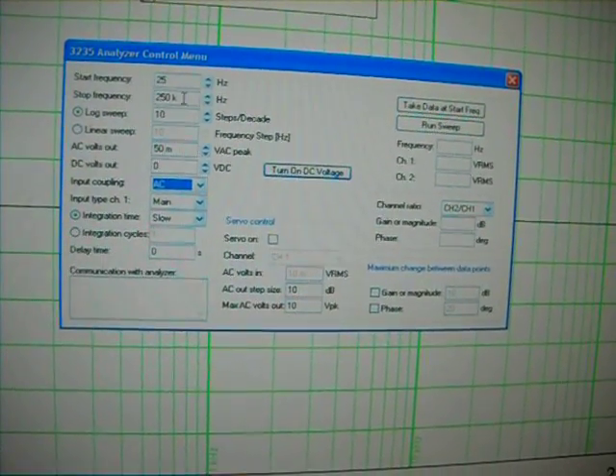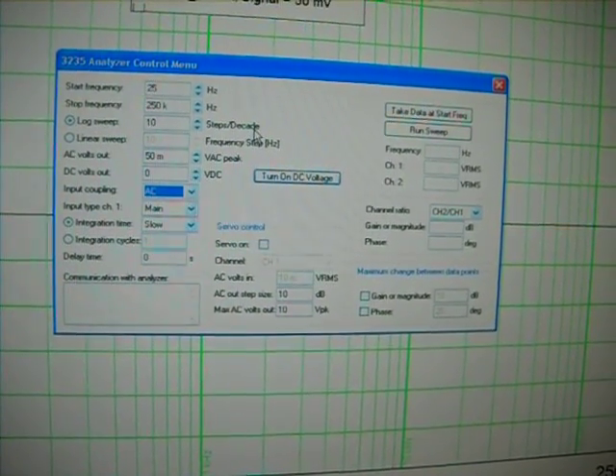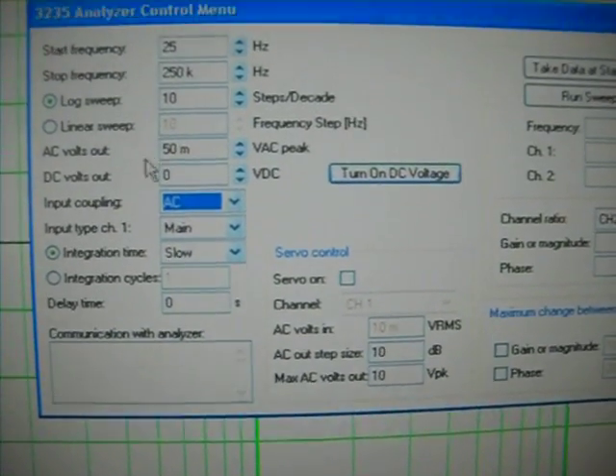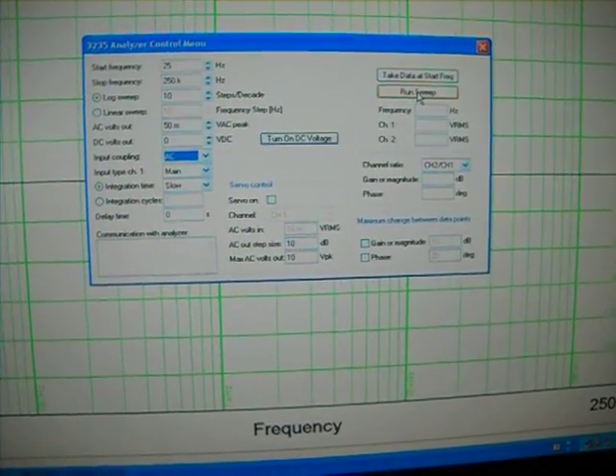Basically, we're going to take a measurement of the stability of the power supply. So we bring up the Venable software and go to Analyzer Control. I'm telling it to sweep from 25 Hz, stop frequency of 250 kHz, log sweep, and I want 10 steps per decade. The other thing you want to do is make sure you drive it with a low enough signal — right now I'm putting in 50 millivolts AC peak. So I can go ahead and press Run.